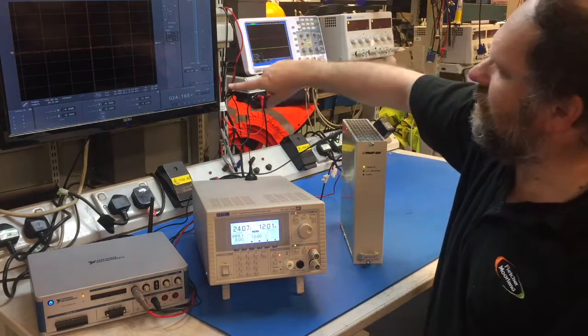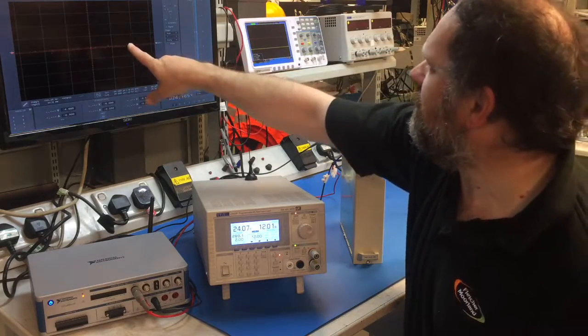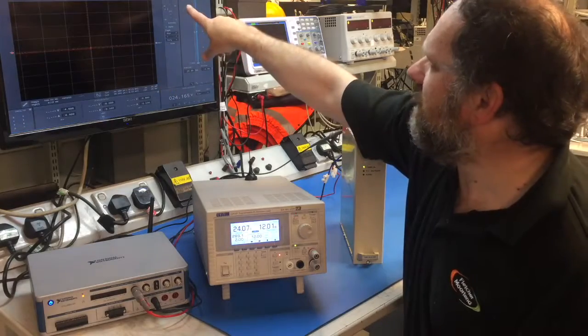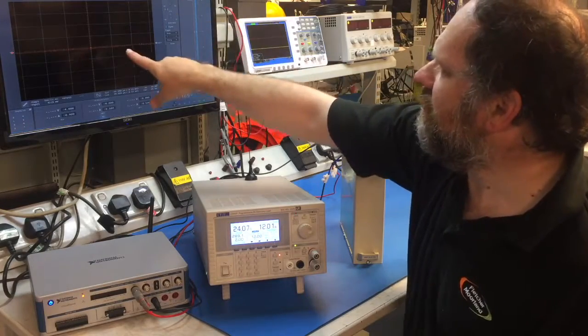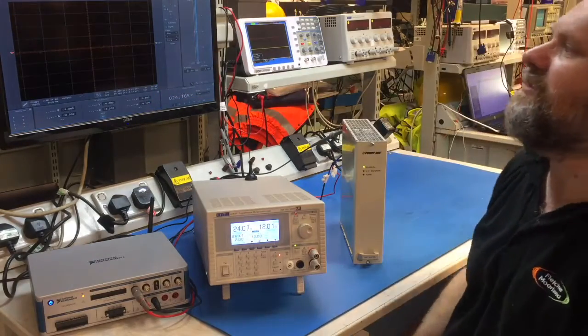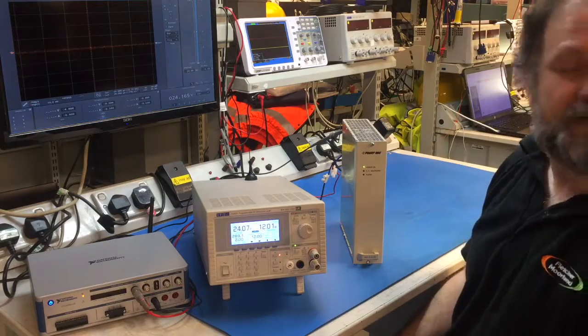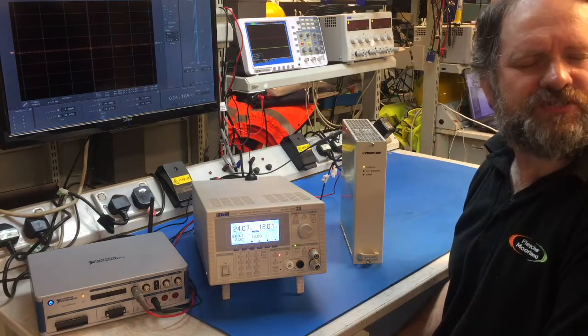So I'm looking at the terminal voltage, and I'm looking at the noise level here at 100 millivolts per division. You can see the noise is really no greater than 20 millivolts peak to peak, and that's within manufacturer specifications.